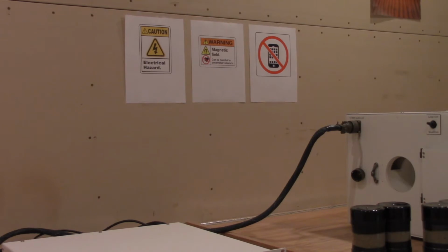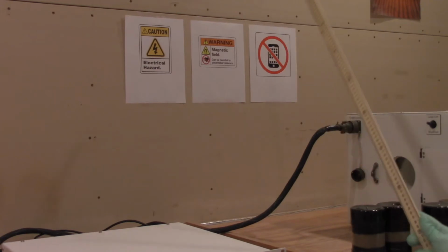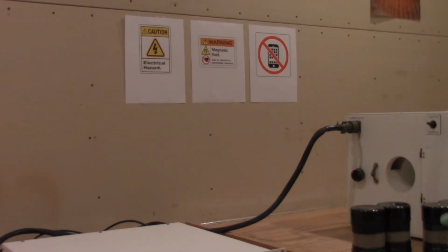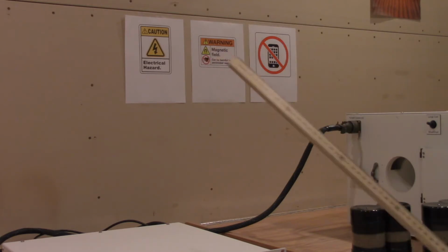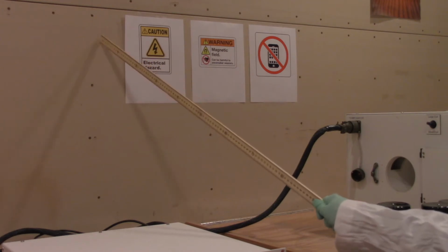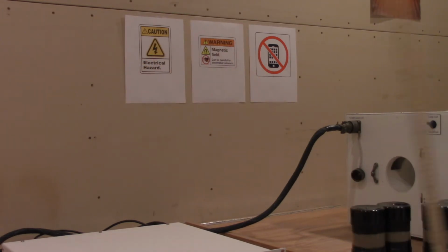As with any NMR measurement, radio frequency noise can be an issue. So generally, you don't have any other equipment running in the lab at the same time, particularly cell phones or anything else that makes RF noise. We try to keep the computer far from the instrument, and it can even be useful to turn off the lights to reduce the 60 hertz power line noise. Our NMR room here is actually a Faraday cage. It's entirely lined with steel, and that helps to keep out some of the other RF noise from the building.